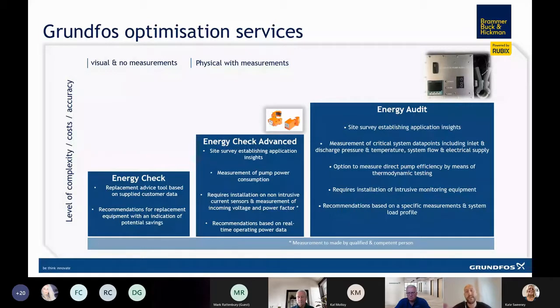So what that does is give us a full load profile of what the system is doing, and the system requirements effectively. That gives us a much more accurate view of what the system requirements actually are, so we can assess whether we can reduce the pump size further if the demand doesn't require the size of pump that's already installed.